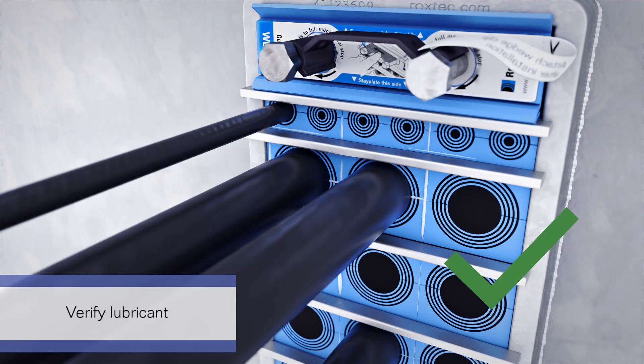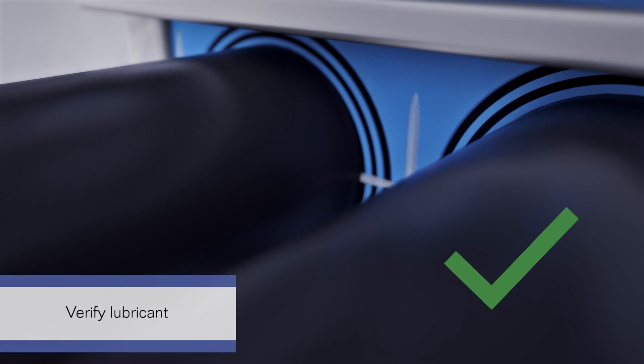If possible, verify that lubricant has been used. Normally, it's only possible to see squeezed out lubricant in recent installations.